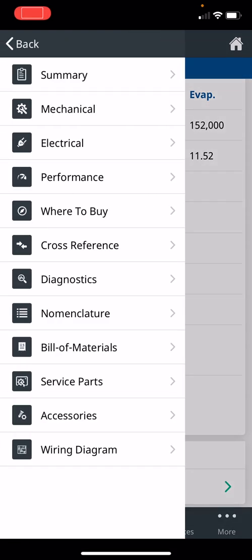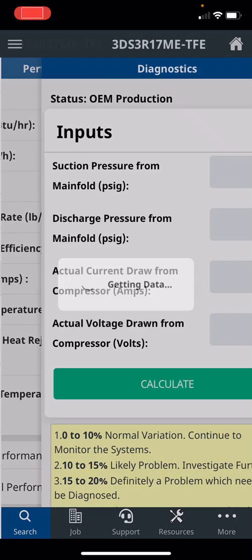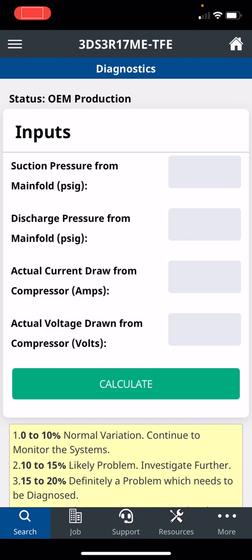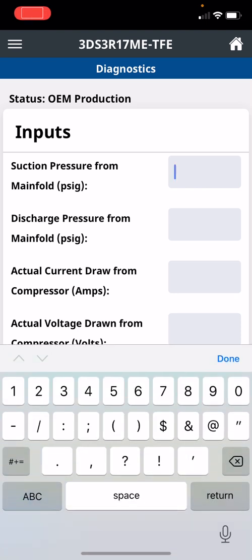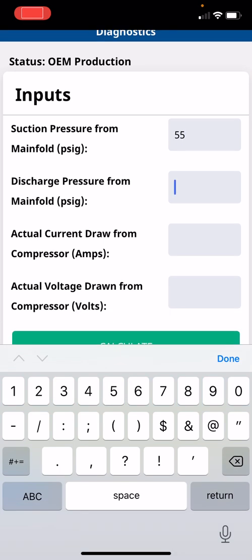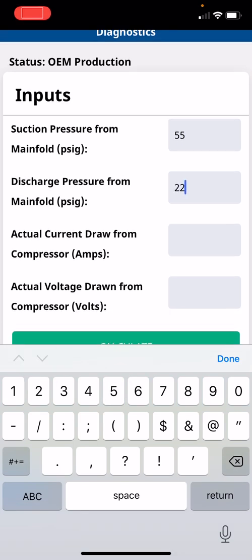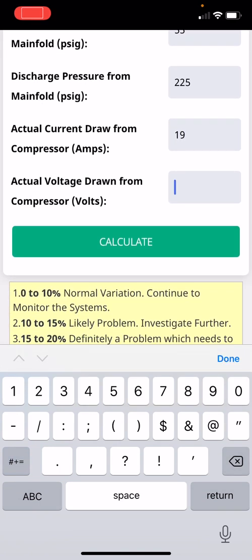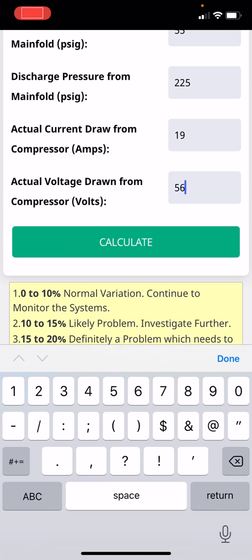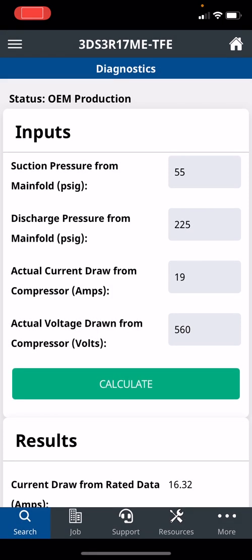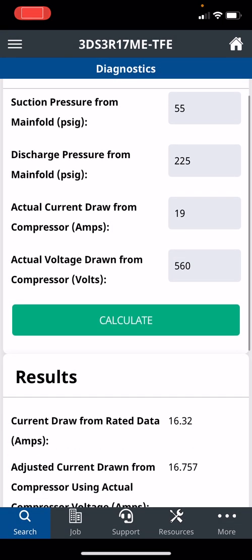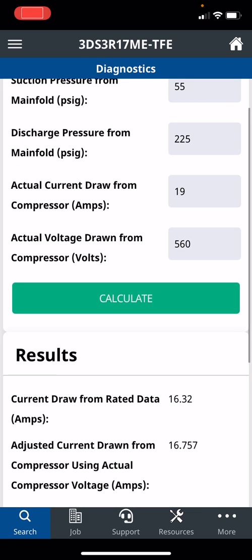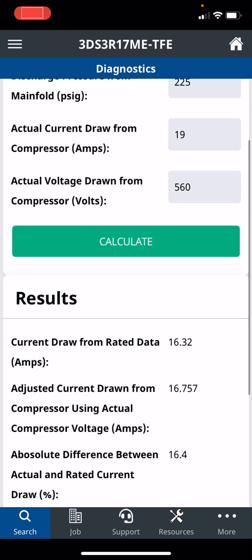Hit the three buttons to go back to the main menu. The next thing is the diagnostics. This feature is such an amazing feature. I wish I had this help when I was in the field. I use it all the time now when I'm in the field supporting contractors. So we'll just throw some numbers in: 55, 225, current draw we're going to just say 19, and we're going to say that the actual voltage is 560. We click on calculate. The current draw from the nameplate should be 16.32.